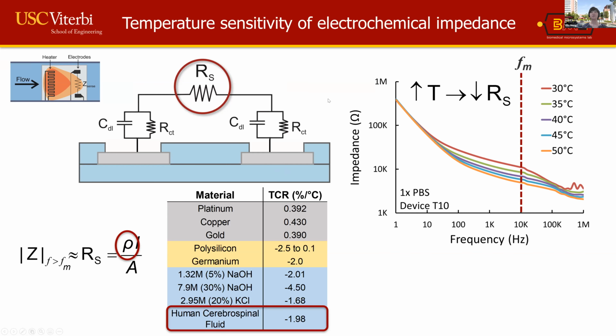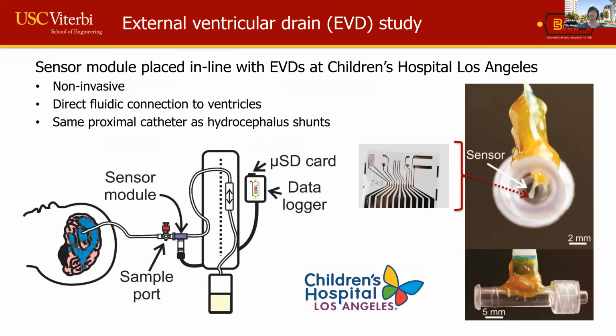It turns out the solution itself, which is human cerebrospinal fluid, is quite temperature sensitive, more so than common resistance temperature detector materials like platinum, as listed down here. So as the heat is carried downstream by the flow, we can detect a decrease in the solution resistance by measuring the electrochemical impedance at high frequency, and that correlates to the increase in temperature. With that, we ran some studies in external ventricular drains at Children's Hospital of Los Angeles, using only the flow sensor in some initial studies.